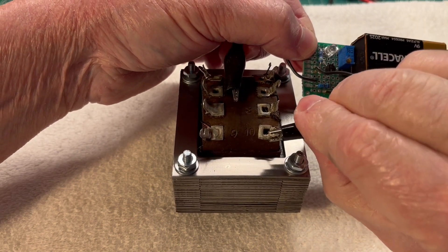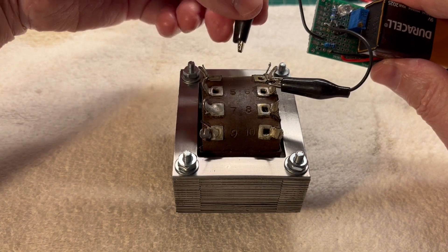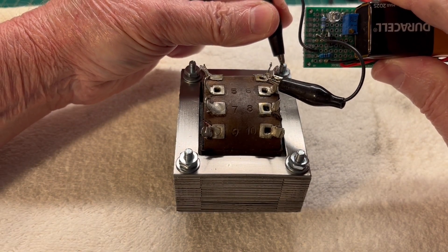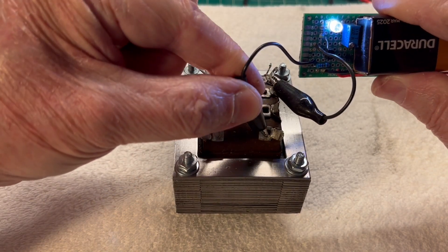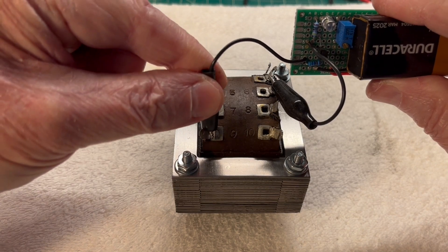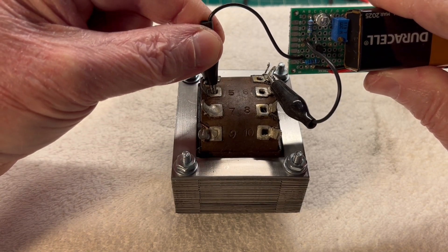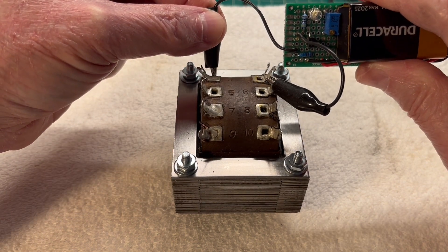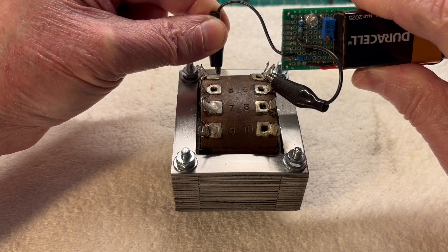Just for the fun of it, we'll check the center tap just to make 100% certain. Nothing to the housing, nothing on four, nothing on eight. Two should illuminate. Shouldn't see anything on nine, seven, five, three, or one. And back to the housing, and we're good.